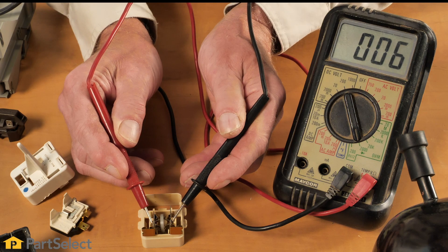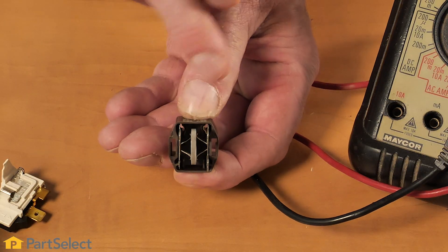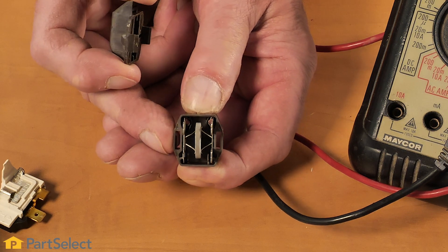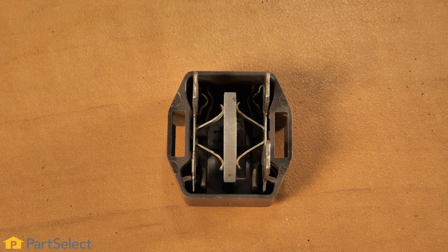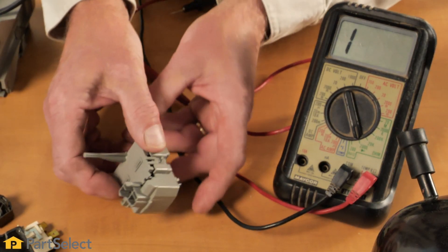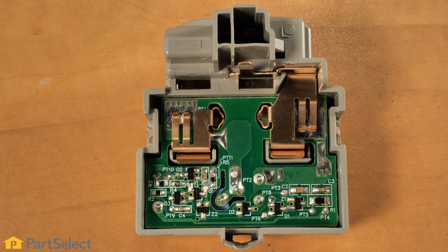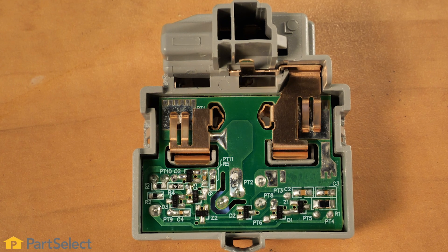If there isn't continuity, we can assume that that device is defective. Other styles of relays may look like this — internally we basically have some type of a thermistor that would measure continuity between both sides. As they heat up, they will go to a very high resistance and drop out that start winding. Some very new styles of these devices use little electronic control boards internally, which are very difficult to check with a multimeter without extensive knowledge of how that circuit works.